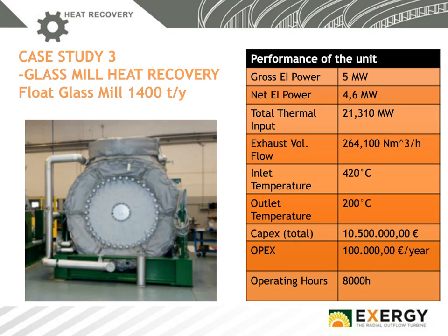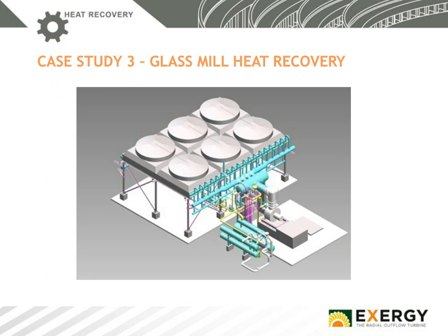Last case study is a glass mill. In the case of the glass mill, again, we have a similar unit in terms of dimension, so it's a 4.6 megawatt net. Here, the flue gas are at the intermediate temperature, so 420 degrees in, 200 degrees out. We have a 10.5 million euro investment and 8,000 operating hours. This is, let's say, a rendering of the system with the 6 fans, air-cooled condenser. Again, it's very similar to the one you've seen before, and this is exactly the plant we have just installed and started up and successfully commissioned in Bulgaria on a glass mill.